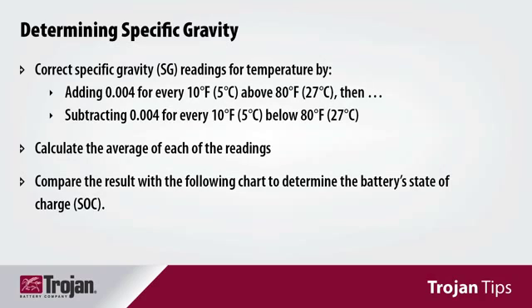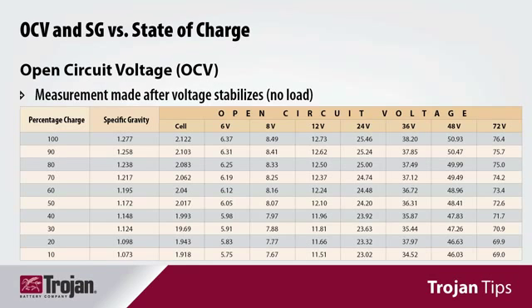Correct specific gravity readings for temperature by adding 0.004 for every 10 degrees Fahrenheit above 80 degrees, and subtract 0.004 for every 10 degrees below 80 degrees Fahrenheit. Calculate the average of each of the readings and compare the result with this chart to determine the battery state of charge.